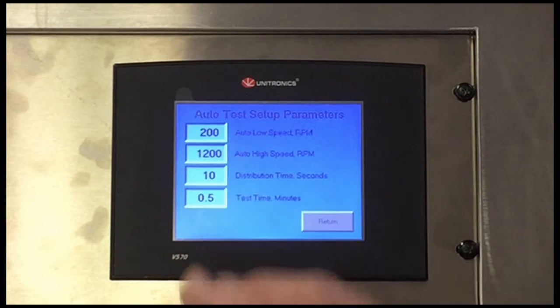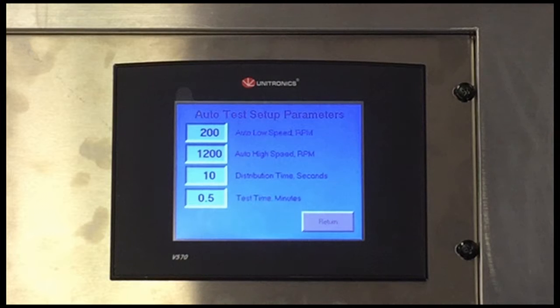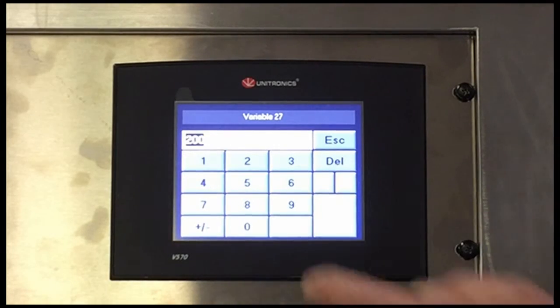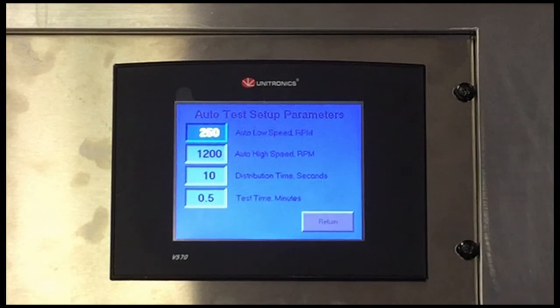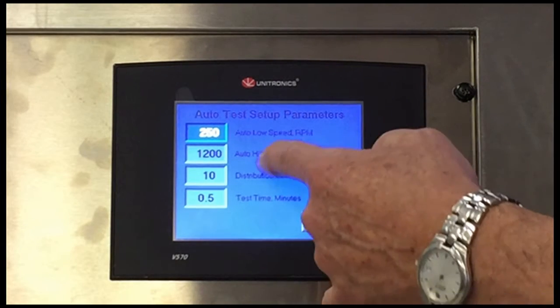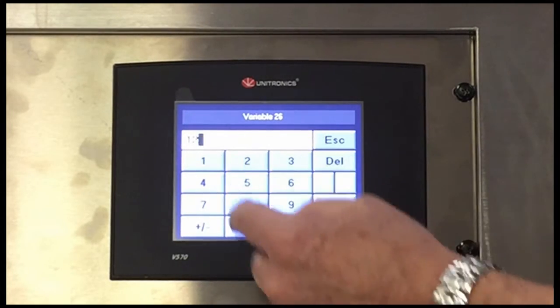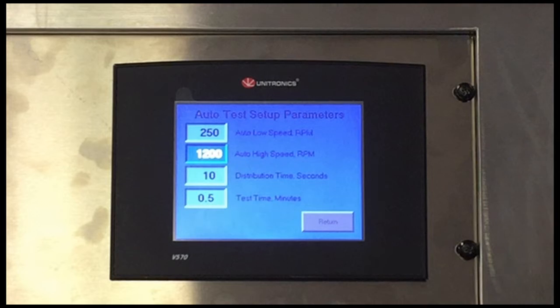Okay? The auto test, if you recall, when we ran the auto test, we did a distribution of 200 RPM. Well, if you look here, this is where that 200 RPM came from. If I wanted to change my distribution speed, I would key that in here. Our actual test speed was at 1200 RPM, and this is where I've keyed that in.